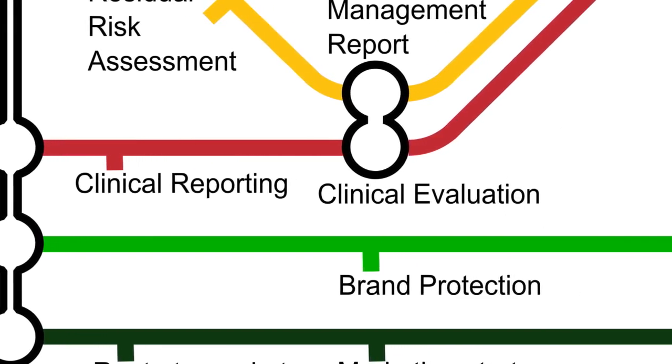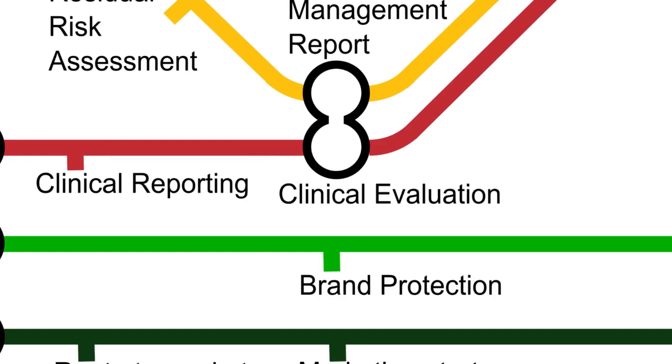The results of your clinical program are typically reported during the industrialization phase of development, leading to the production of a clinical evaluation report. This documents the fruits of your clinical evaluation, the investigations undertaken, and how their results support the safety and efficacy of your medical device. As I mentioned earlier, you'll be taking care to ensure that the medical device regulation requirements are comprehensively covered. There's a close link here with risk management reporting, particularly to support the verification of risk mitigations.